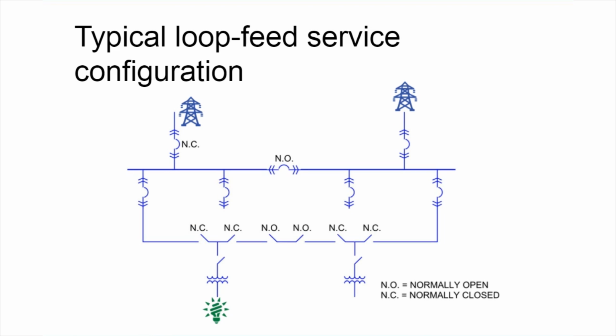Another approach that we use on some of our more complex and critical projects is a loop feed system. Here we've got multiple utility sources coming into the site, and they're feeding two halves of a distribution bus with a normally open switch in between, which would close automatically on loss of utility power. But we're also loop feeding those buses out to the loads and the unit substations that actually deliver power to the buildings. What this allows for is if any feeder on site goes out, we're also able to pick back up load from the other side.